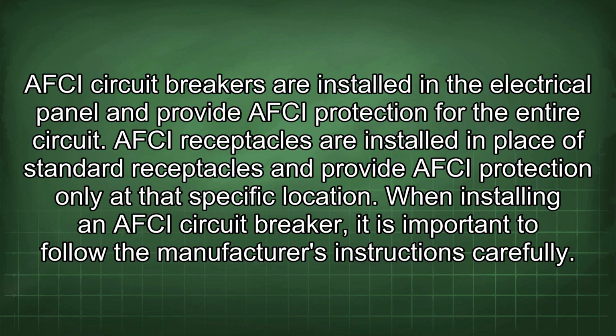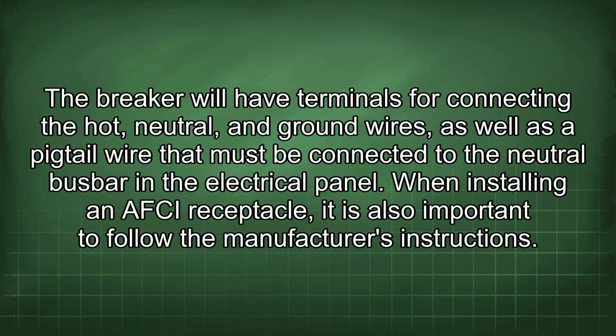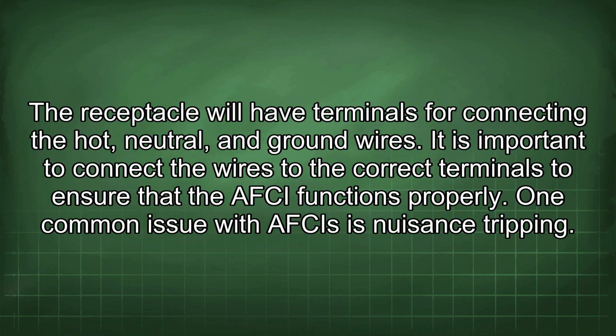When installing an AFCI circuit breaker, it is important to follow the manufacturer's instructions carefully. The breaker will have terminals for connecting the hot, neutral, and ground wires, as well as a pigtail wire that must be connected to the neutral busbar in the electrical panel. When installing an AFCI receptacle, it is also important to follow the manufacturer's instructions. The receptacle will have terminals for connecting the hot, neutral, and ground wires. It is important to connect the wires to the correct terminals to ensure that the AFCI functions properly.